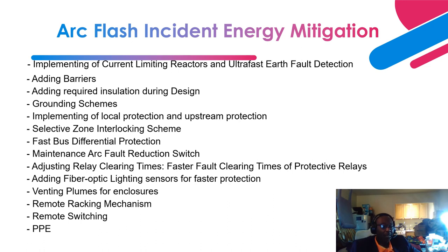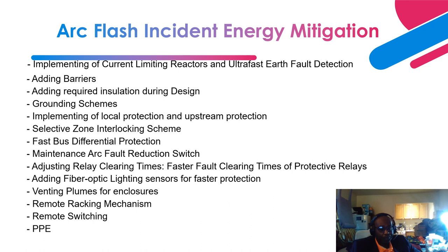Next is a remote racking mechanism, which allows the maintenance worker to be far away from the switchgear during racking operations. Next is remote switching — a SCADA system where wiring goes through an RTU to a SCADA or DCS system, allowing you to switch the breaker in and out from a remote location without having a worker in close proximity to the switchgear. Finally, PPE — as a last resort, having the required PPE and following the required working distance.